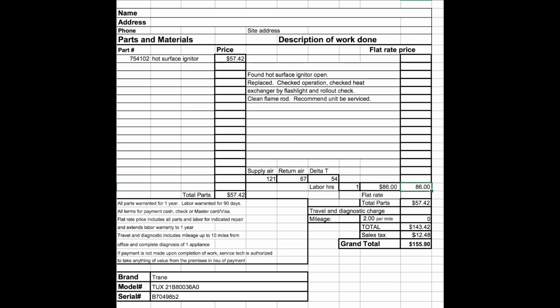I clean the flame rod—I clean flame rods and anything with a flame rod anytime I service a unit. I also recommend the unit be serviced, so you've told the customer it should probably be serviced annually. That's kind of a CYA thing—if they later say, 'why didn't he tell me it should be serviced?' well, there you did.